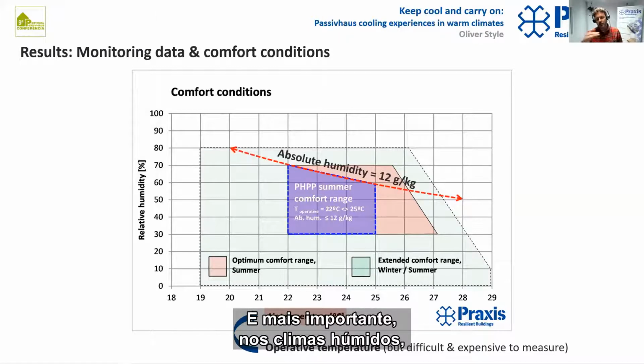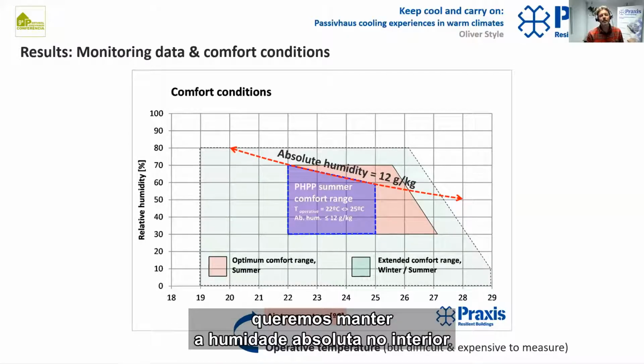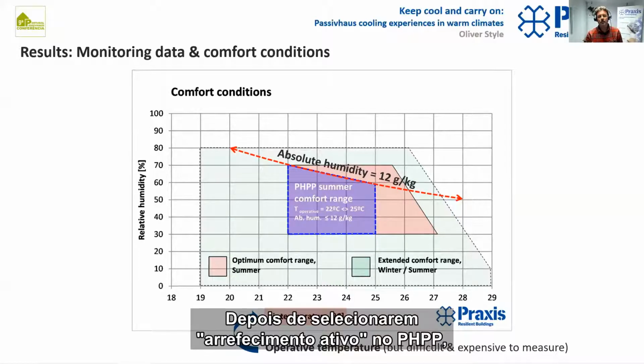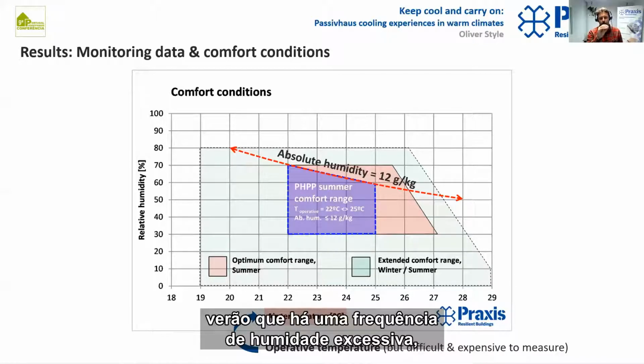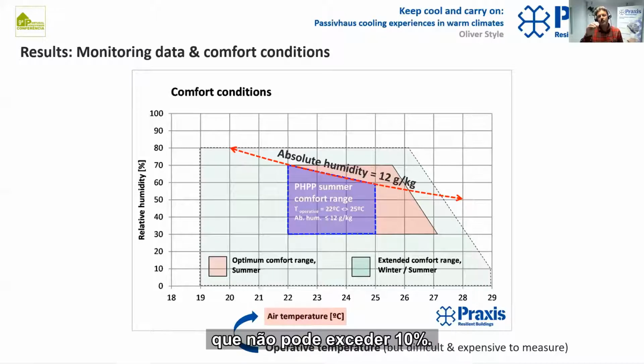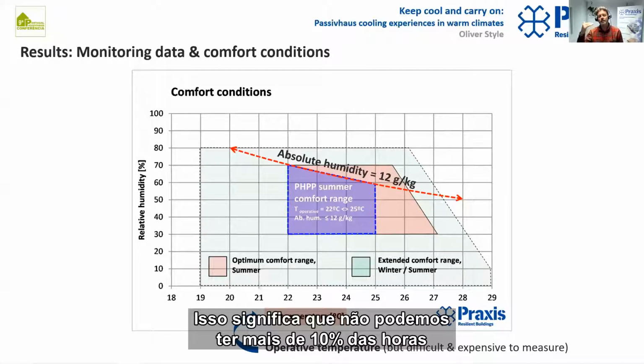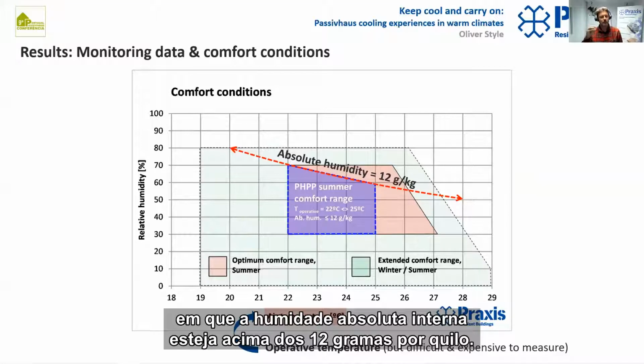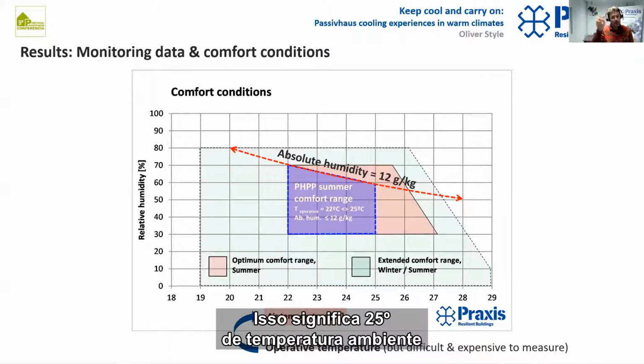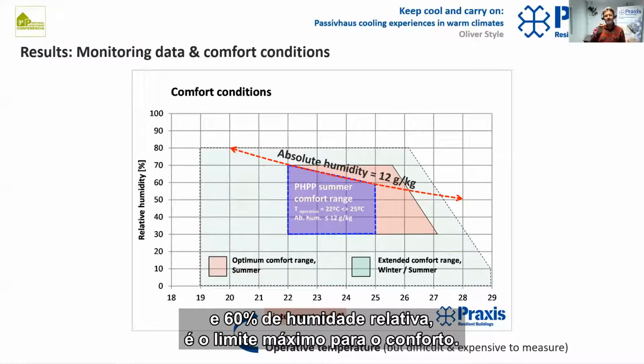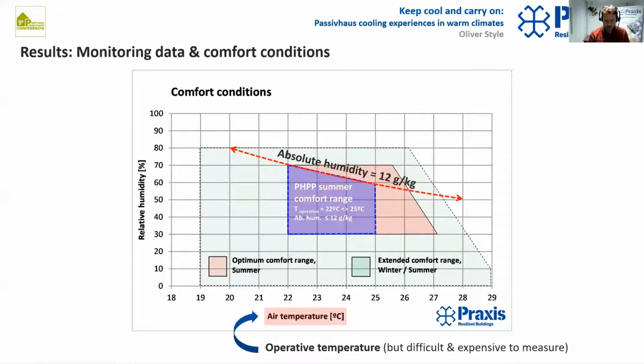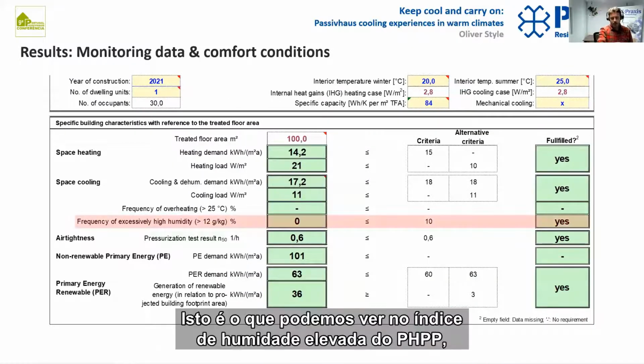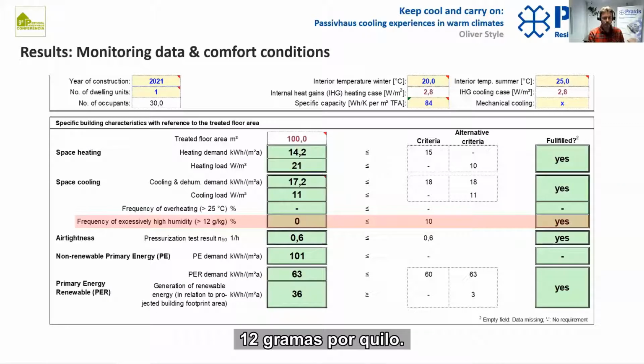And most importantly, in humid climates, we want to try and keep indoor absolute air humidity below 12 grams per kilo. Okay, so once we select active cooling in our PHPP tool, you'll see that there's that frequency of excessive humidity which can't exceed 10%. So that means that we can't have over 10% of hours in which the internal absolute humidity is greater than 12 grams per kilo. That means that 25 degrees operative temperature and 60% relative humidity is about the upper limit for comfort. Okay. This is what we can see in the high humidity index on the PHPP tool of 12 grams per kilo.